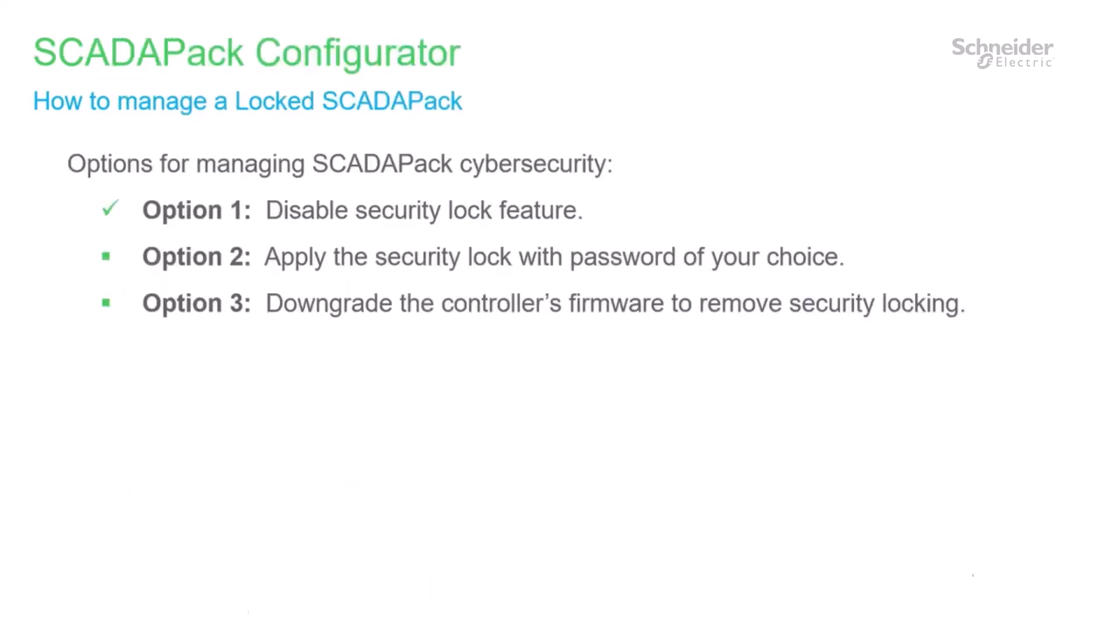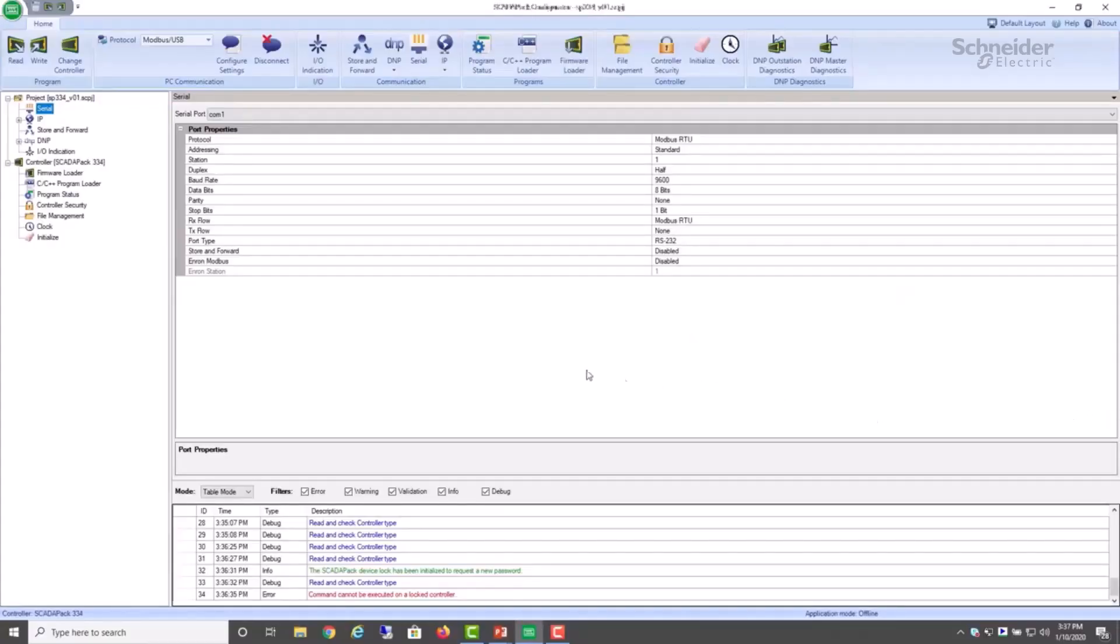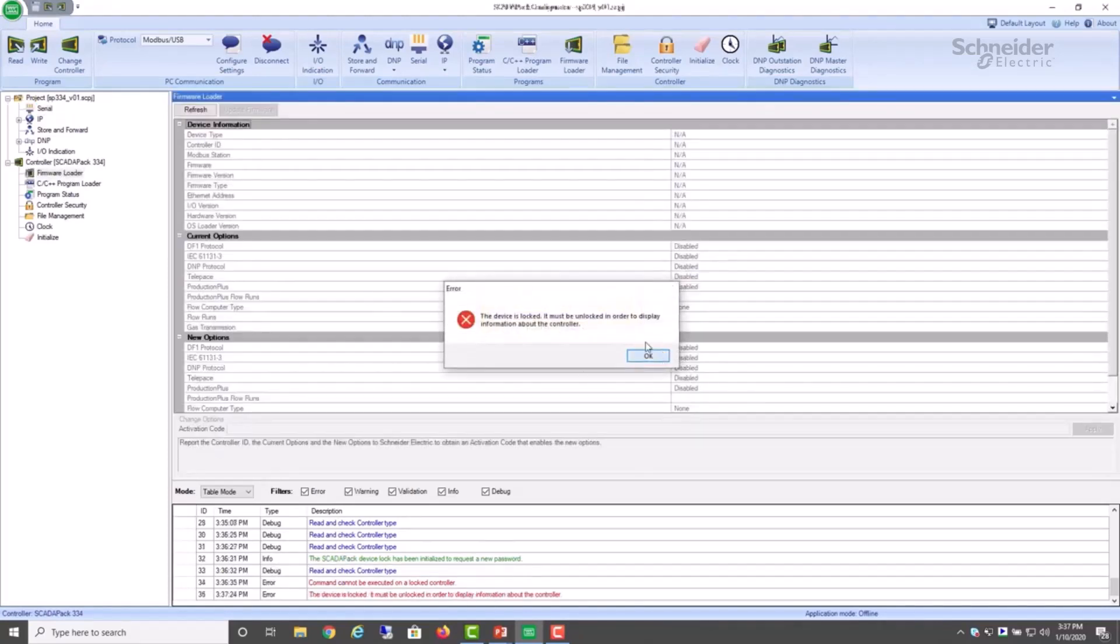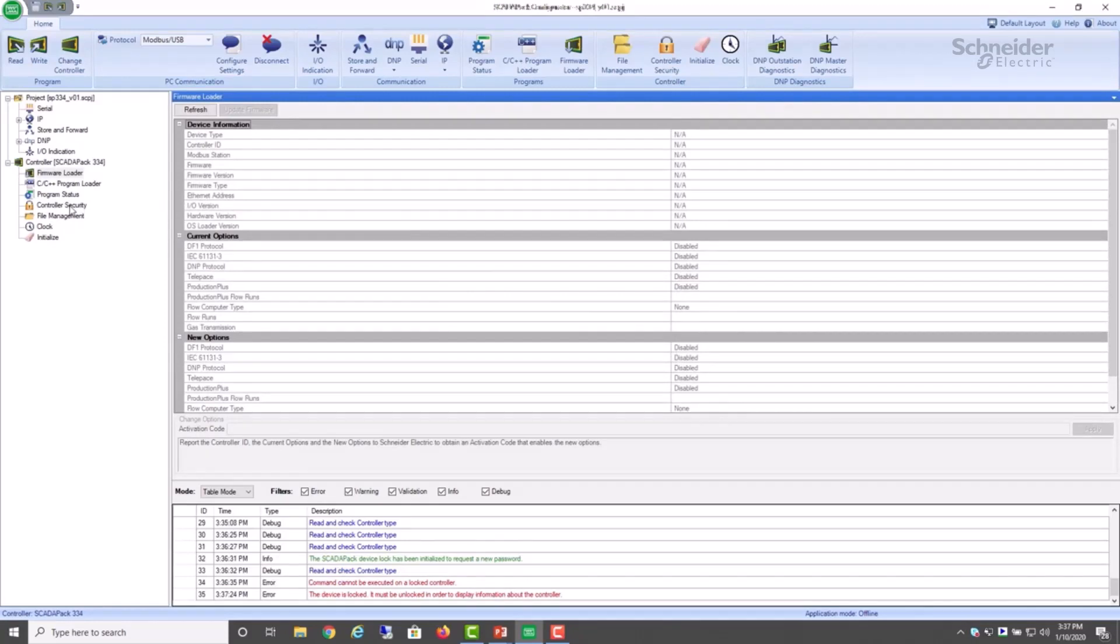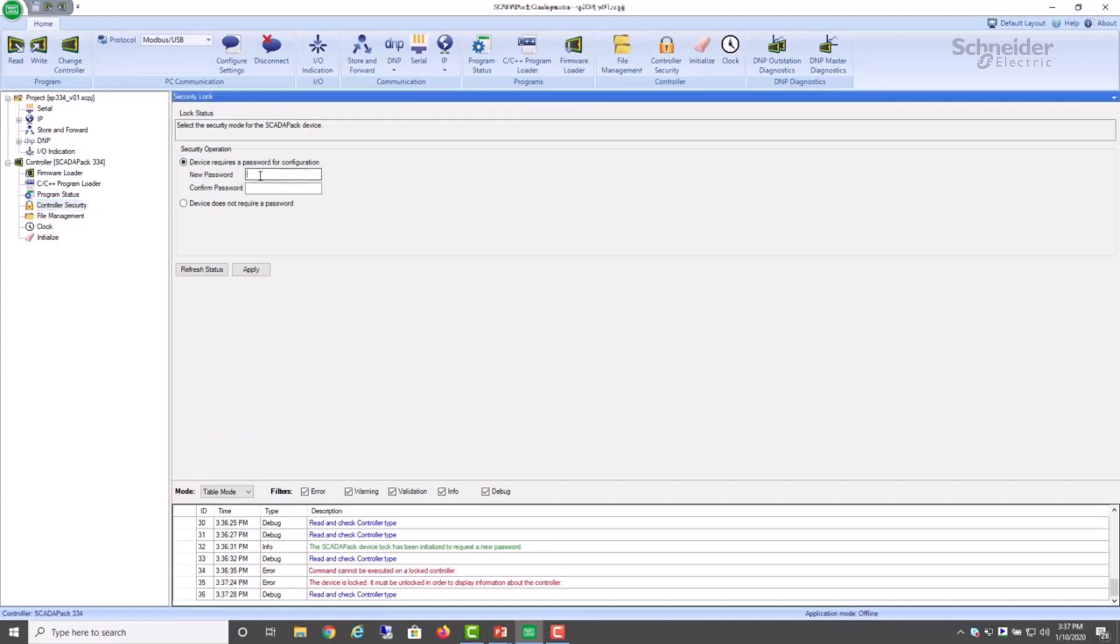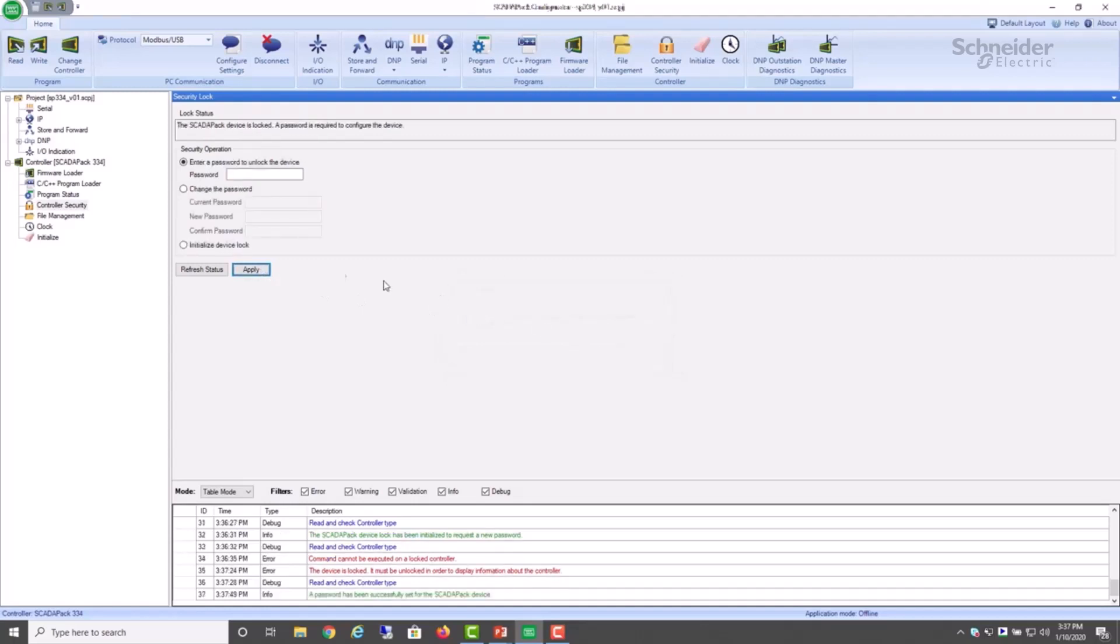Looking at option two now, applying the security lock. Let's switch to SCADA pack configurator. So once again, I have attached a new SCADA pack. And if I select any command, I see that the controller is locked. So the way to approach this is we go to the controller security dialog. And this time, instead of disabling the password, we'll enter a password. It must be eight characters in length or more. And now it says that we have been successful in applying this password.